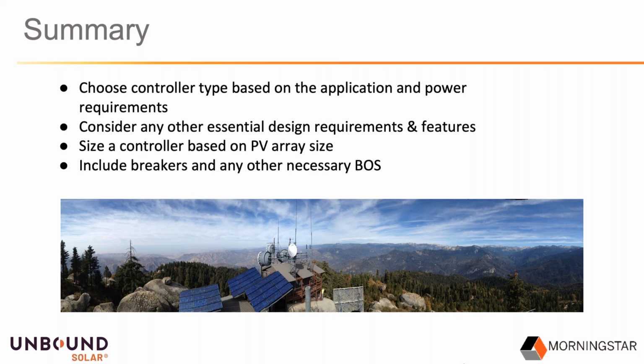So in summary, you choose a controller based on the application and power requirements. MPPTs are usually bigger power requirements. PWM is typically 1 or 2 panel smaller requirements. Consider any other essential design requirements and features, things like, is it active or passively cooled? Do you need to communicate with it? Certifications, and just anything else that might be required. Size a controller based on the PV array size, using the processes depending on if it's PWM or MPPT that we showed previously, and then add any breakers or other necessary balance of system components.